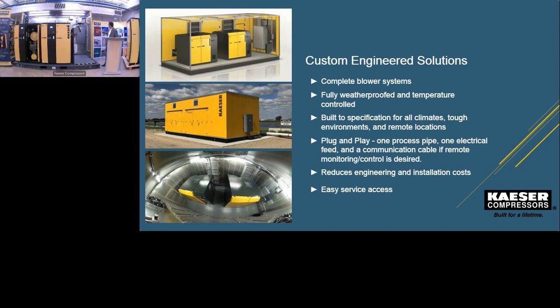So as I mentioned before, on this enclosure system, we have the blowers, we have the power being distributed. We also have the potential for louvers. These louvers can be fixed. In this case, they are automated louvers, which are sensing the room temperature. So as the temperature in the room goes up, the louvers open, and as it cools down, they close. On the far side, we also have an enclosure fan. This allows all the heat that's being rejected from these machines to be pulled out, and so it's not recycled into the enclosure.